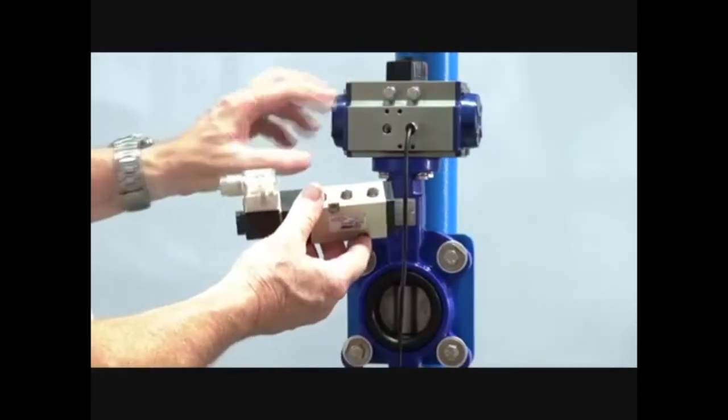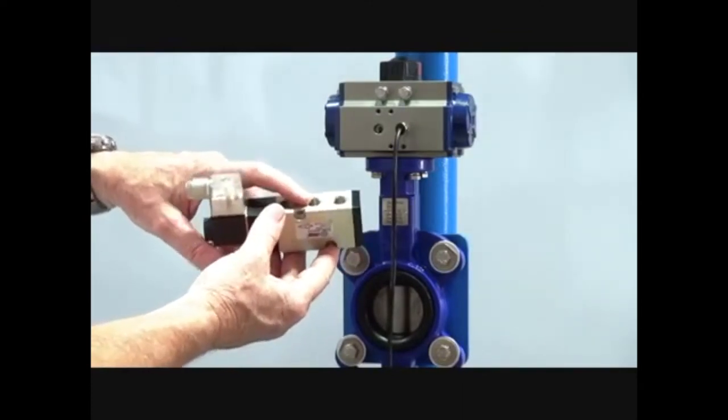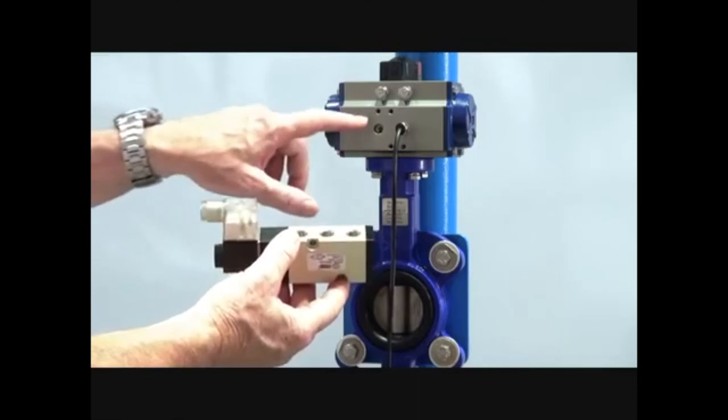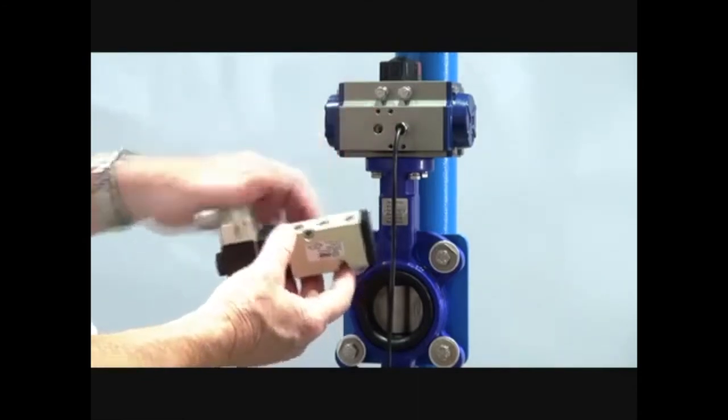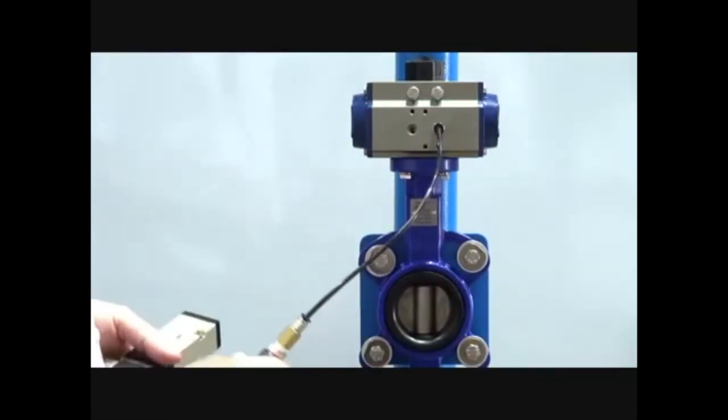Filtered and lubricated air goes to both ends. The spring is purely for a fail-safe function, so that in the case of power failure, the valve will close under the action of the spring.